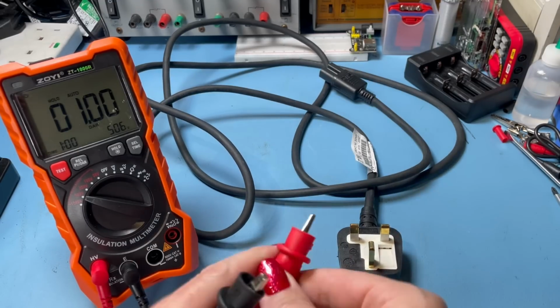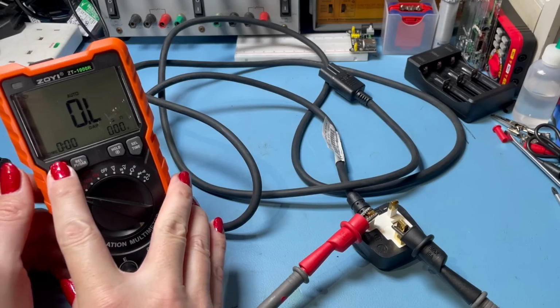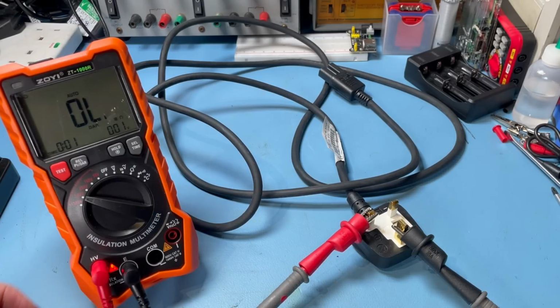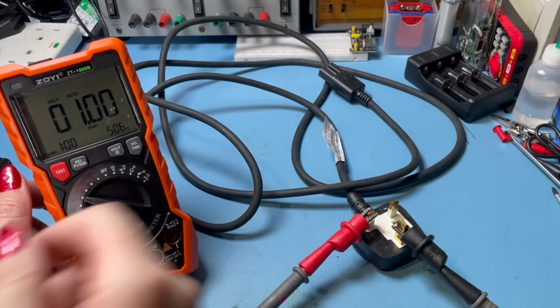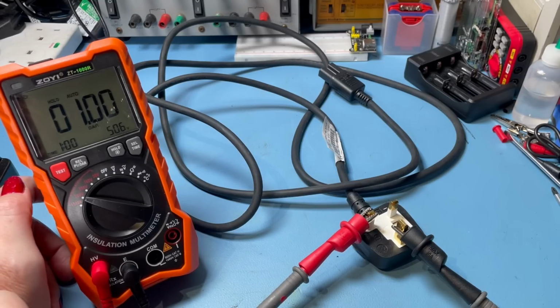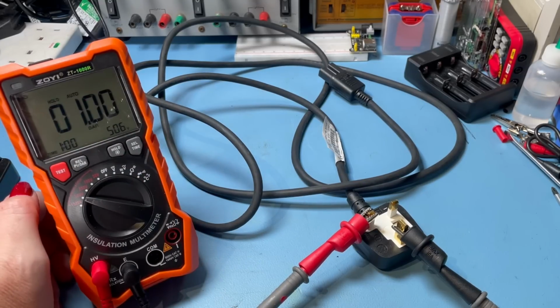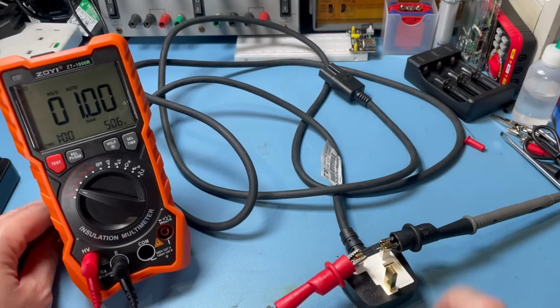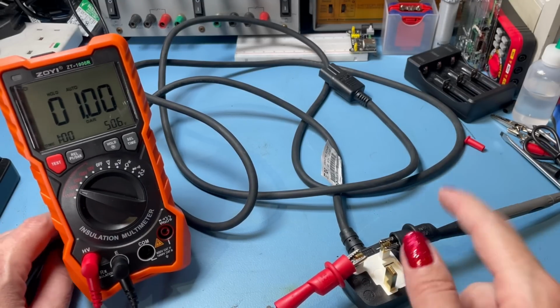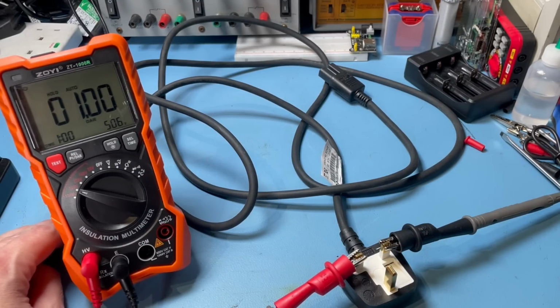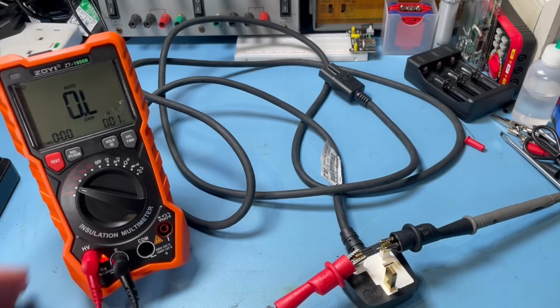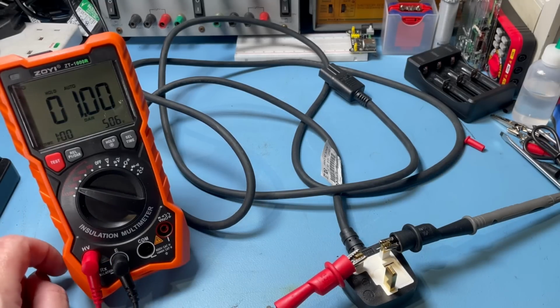We're now going to go for neutral to earth, 500 volts, DAR. Let's go. Okay, so we got 1.00 again there, neutral to earth. Same reading we had on live to earth. So we're going to do one more test on this kettle lead, which is going to be live to neutral at 500 volts. Go. There we go, 1.00 again.